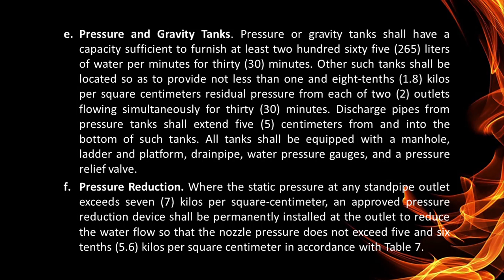Pressure reduction. Where the static pressure at any standpipe outlet exceeds 7 kilos per square centimeter, an approved pressure reduction device shall be permanently installed at the outlet to reduce the water flow so that the nozzle pressure does not exceed 5.6 kilos per square centimeters in accordance with Table 7.